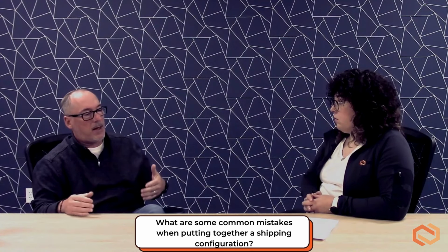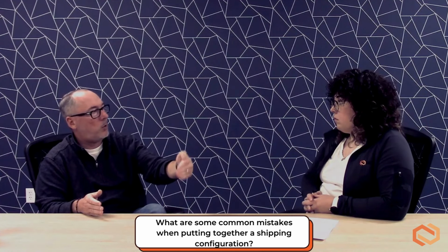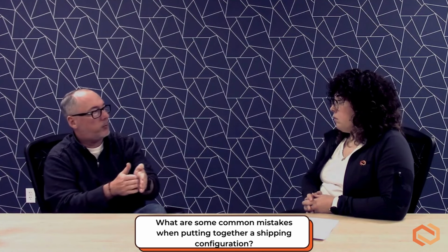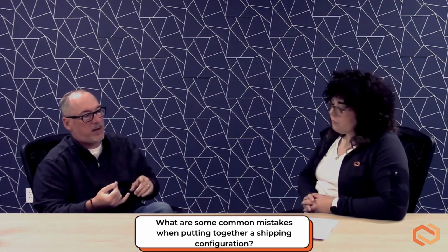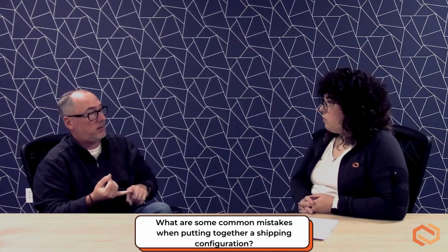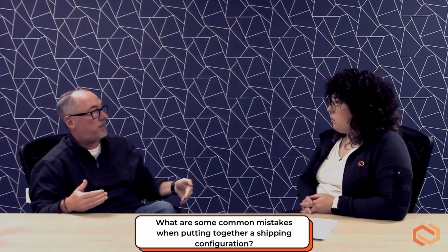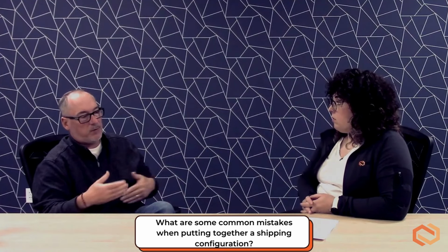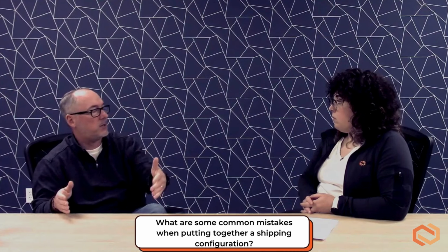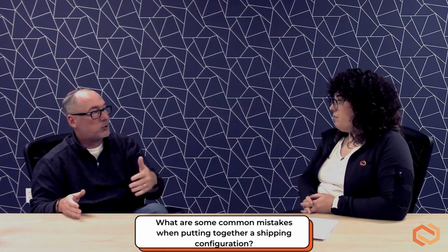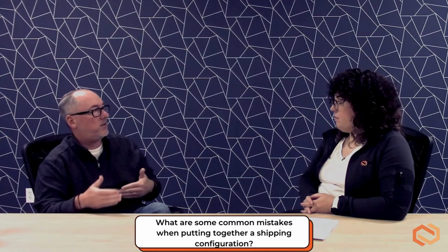Second aspect I see a lot is a lot of these packages are in there. They may not get an abrasion hole from the corrugated, but they will get abrasion issues directly from touching one another. Especially, again, remember we talked about the type of packaging, the type of product, right? Certain products lend themselves better to specific types of packages. So again, if you have a multi-port product and you're putting them in a pouch and you're putting 5 or 10 of these pouches in a corrugated shipper that has no shelf boxes, you're potentially looking for problems, right?